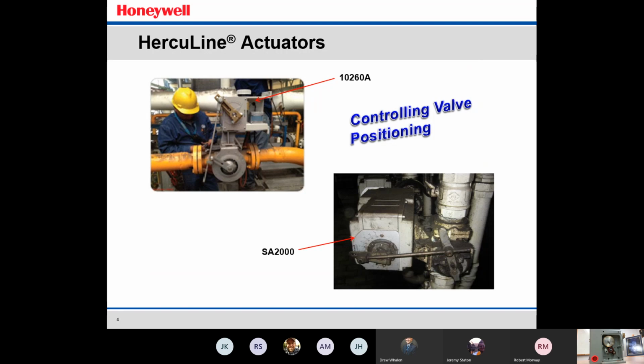Here's a couple examples of actuators out in the field and how they're mounted onto, I believe the top one is possibly a port valve, but for all intents and purposes, a butterfly valve with a little bit better accuracy. And you can see the 10260 is mounted on the top, and then it has a linkage assembly that connects the crank arm down to the butterfly valve. There are manufacturers out there for these butterfly valves, like North American, Maxon, several others, that actually have adapter brackets for both the Herculine 2000 and the 10260. So if you get into applications where you have one of these butterfly valves, you could usually ask the manufacturer and they'll supply an adapter kit or a mounting plate to mount the actuator on top of the valve.